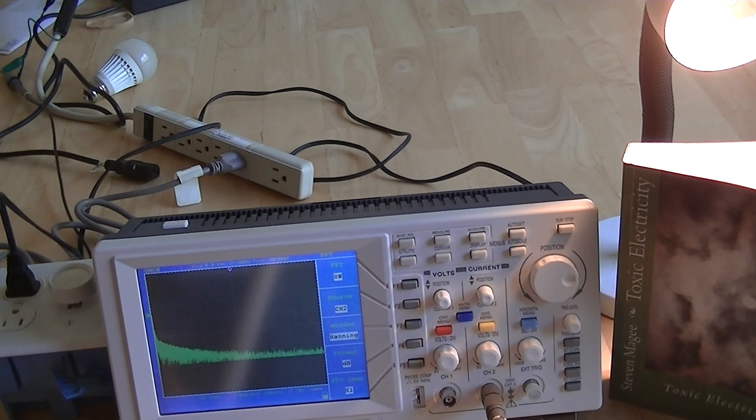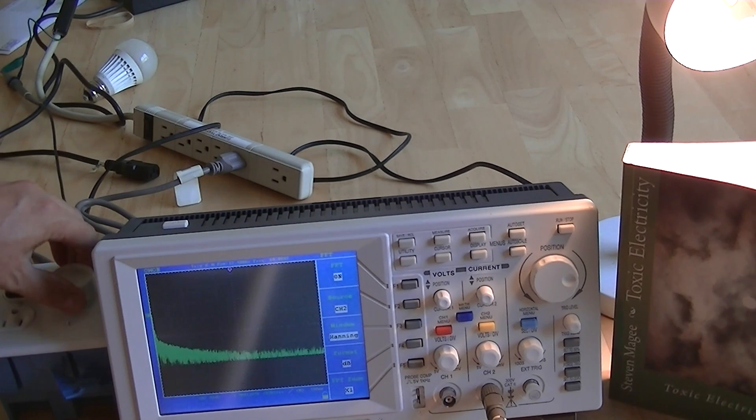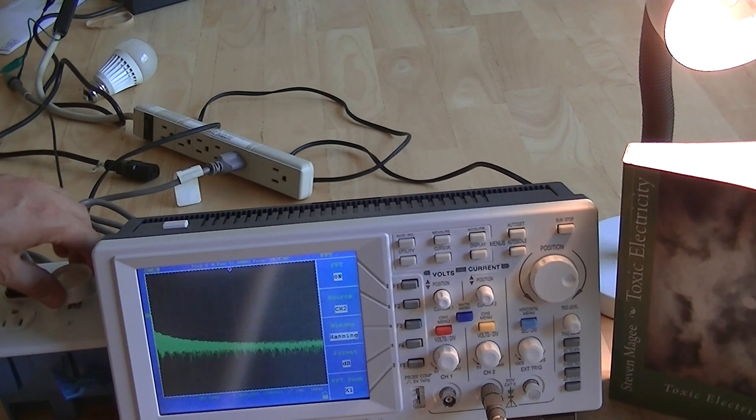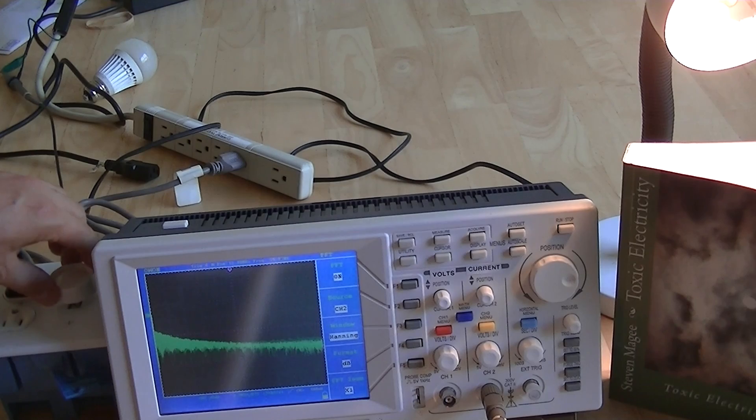So let's vary the lamp dimmer and see what we get. So you can see the harmonics vary according to the dimming setting that you have. And you can get quite extensive harmonics simply by changing the dimming setting.